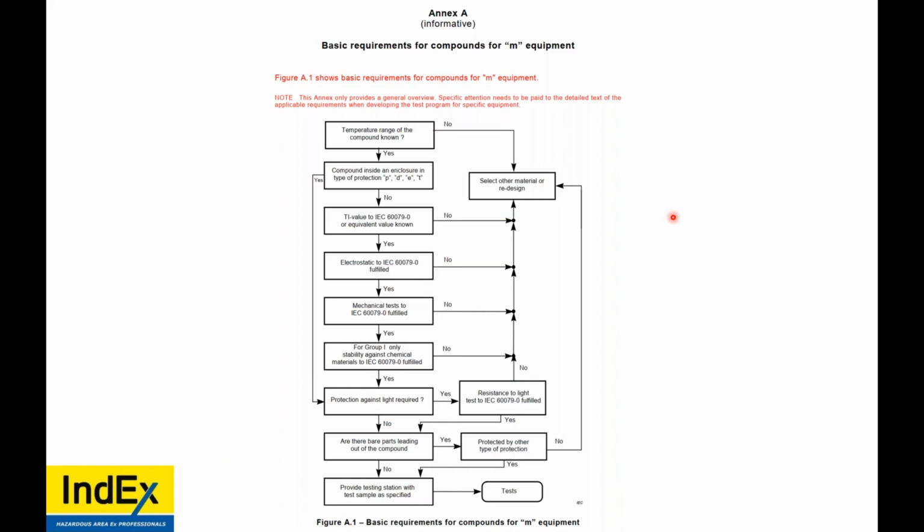This is for the manufacturers of how to select the correct type of compound. Temperature range of the compound known? No. Well, select another material or redesign. Yes. Is the compound inside of another EX protection technique? Yes. Everything's nice and easy. If no, then they have to do other tests such as TI, I'm not sure which that one is, electrostatic test, mechanical test, group 1 tests, or just put in another EX protection technique and nice and easy.